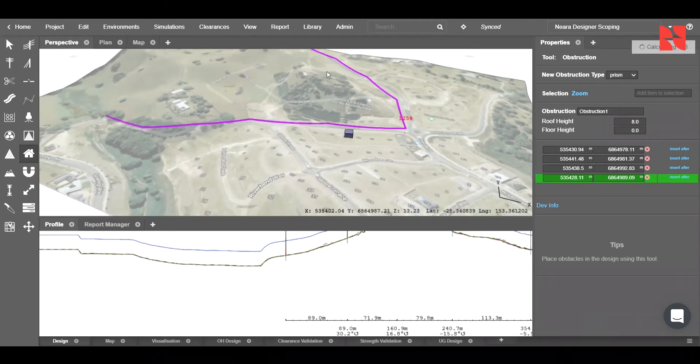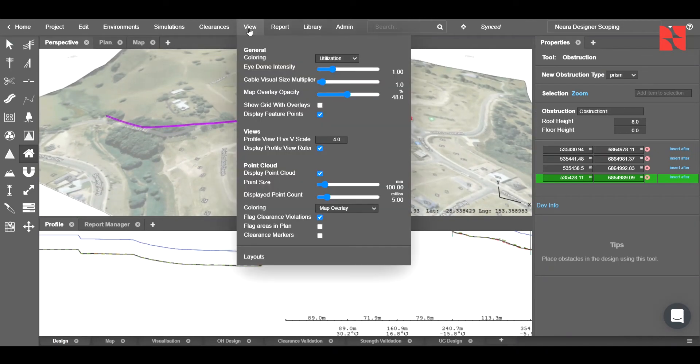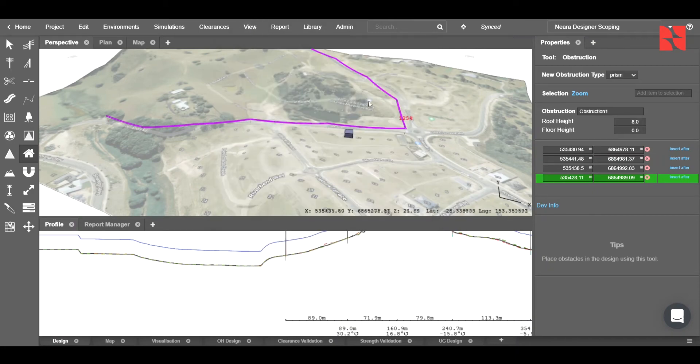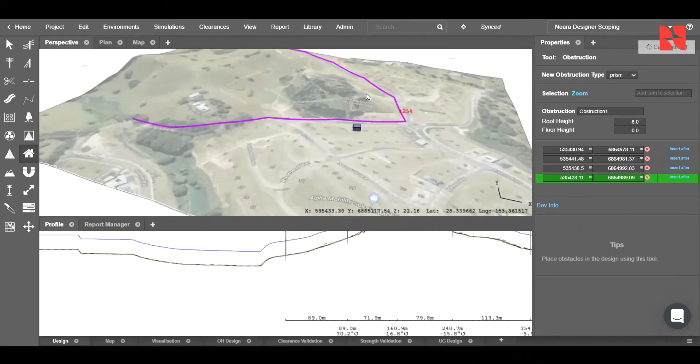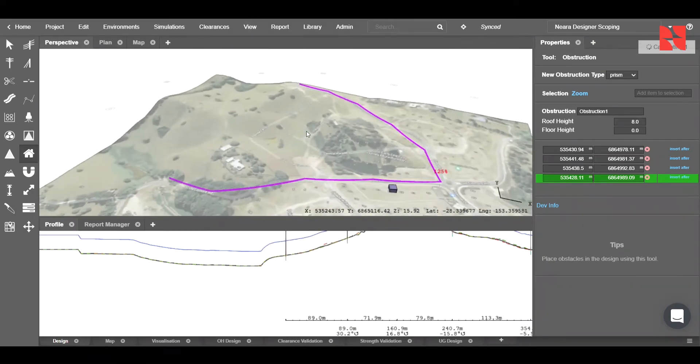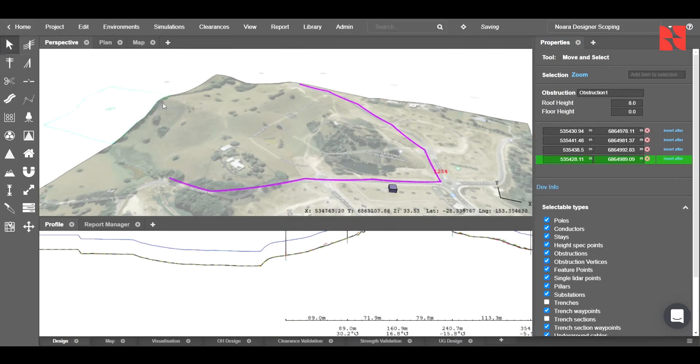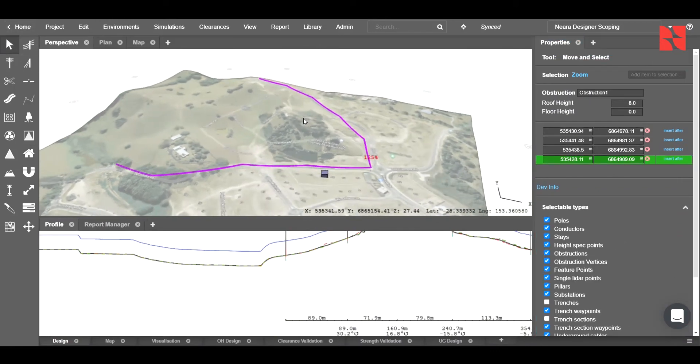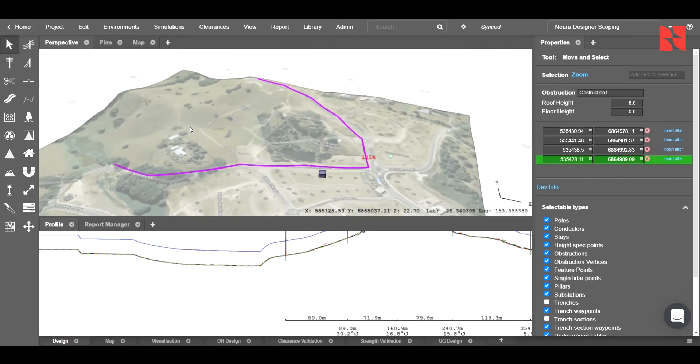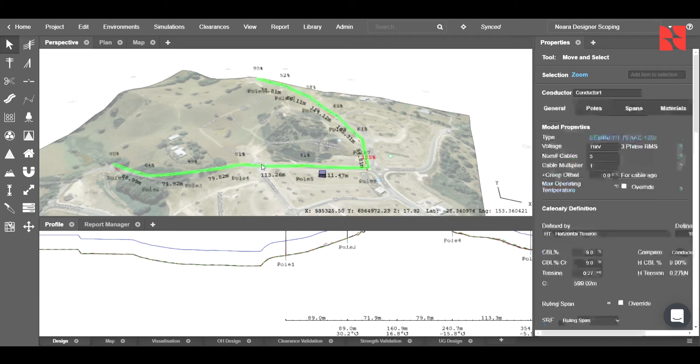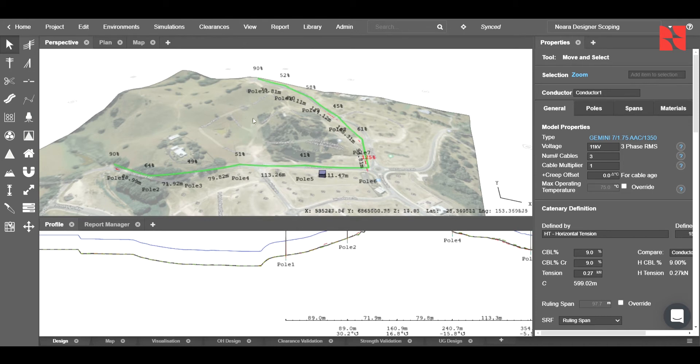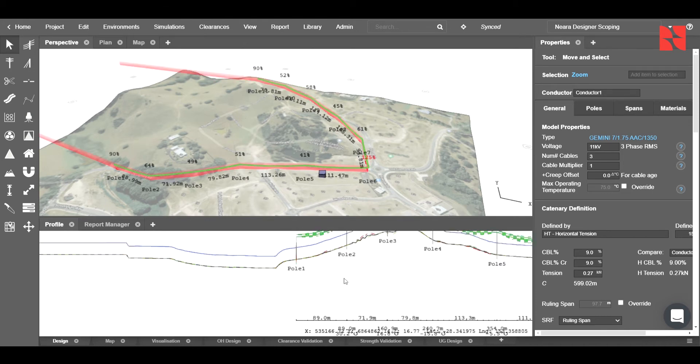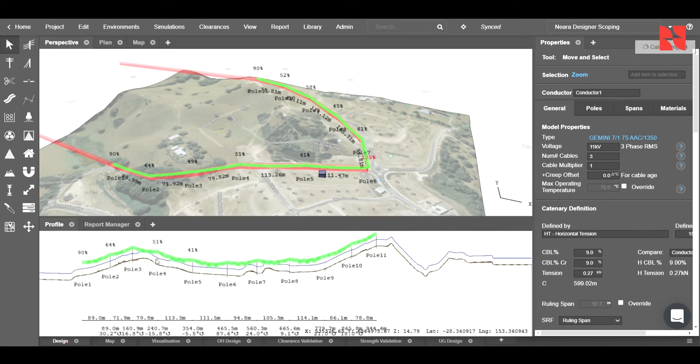Now, by turning on the view and turning on utilization, we can look at the tip loads of our span. We can see that this is showing the tip loads where they are exceeded for our entire network. However, by clicking on the conductor span, we're also able to see the utilization of each of the poles. We can see that we have three poles that need addressing. Those are going to be our end poles, and also the pole in the middle.